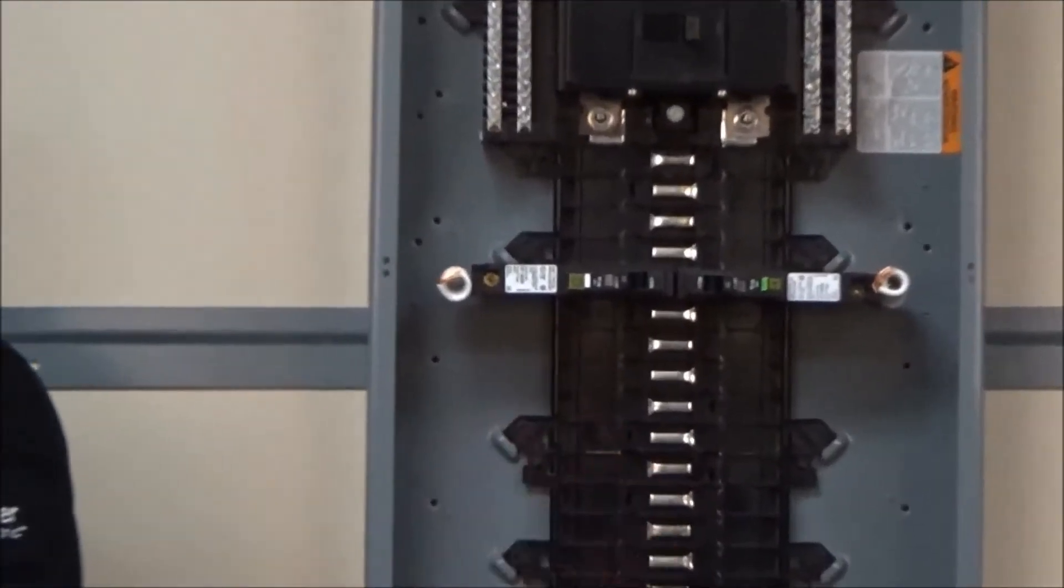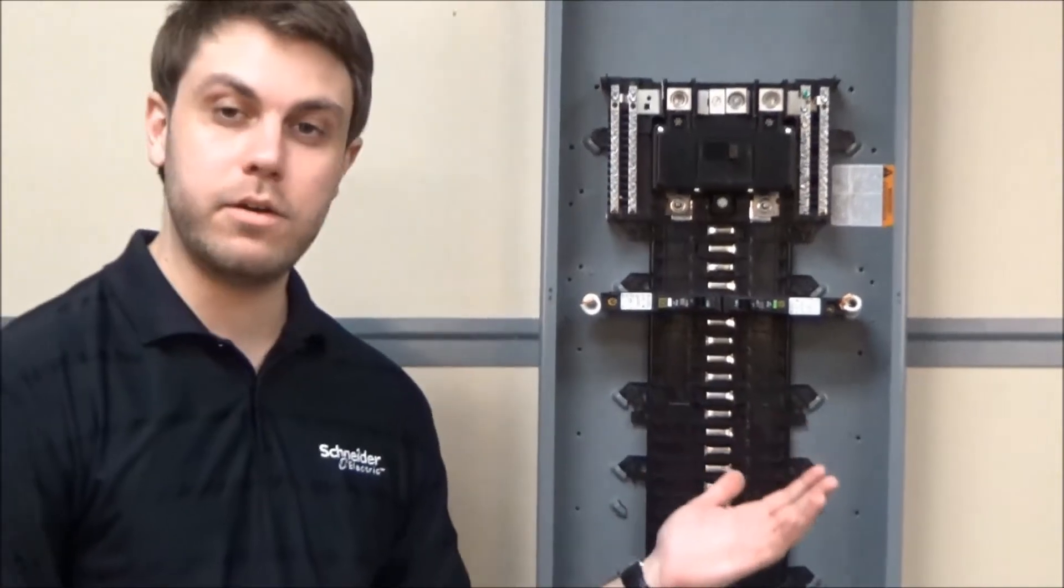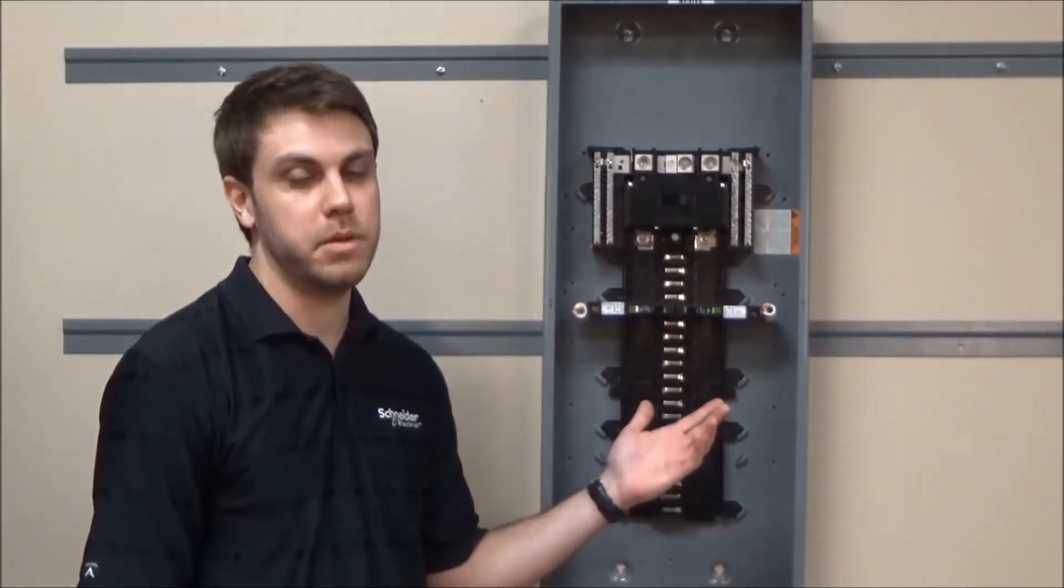The other arc fault breaker we have is the one with the white test button. This is what we call our CAFI or combination arc fault interrupter. This detects the parallel arcs that the green test button breakers detect plus series arc. A series arc is an arc that occurs on a single wire.